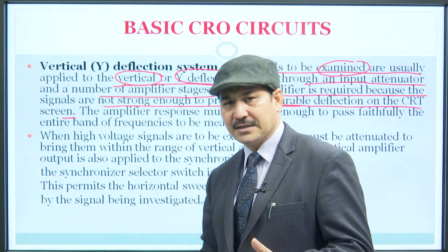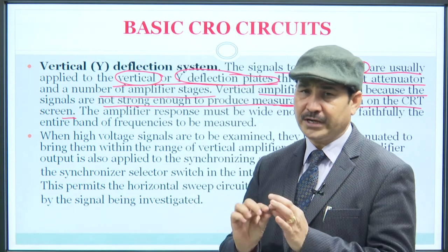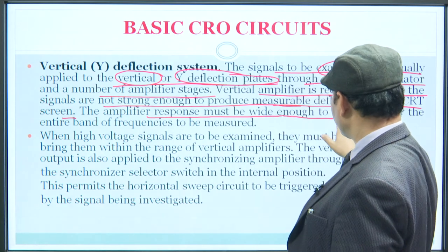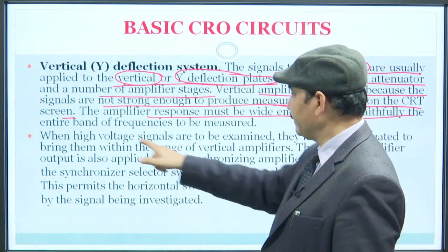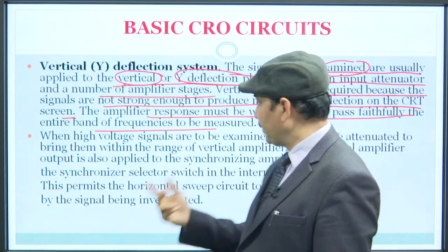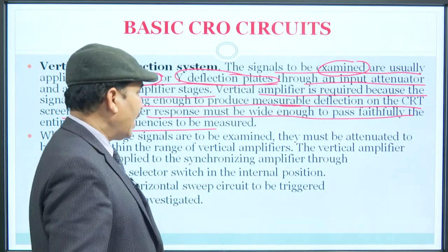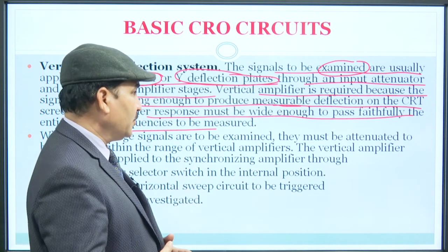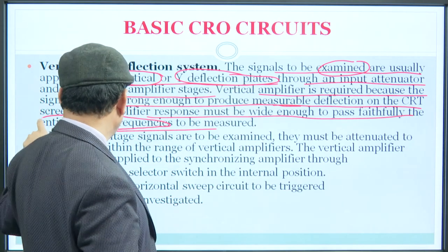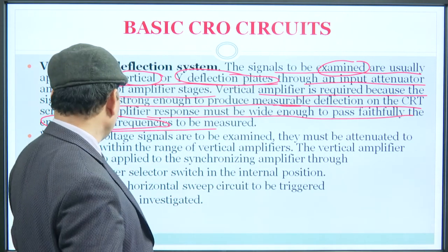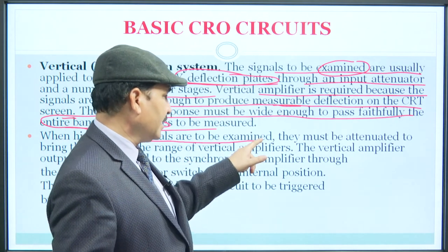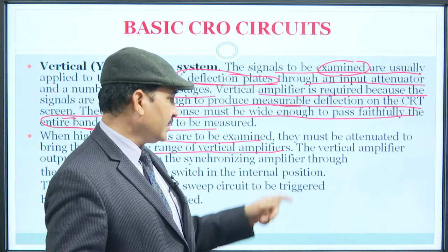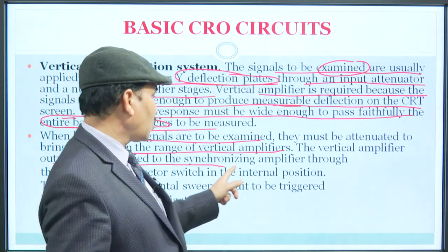If the signal is very large, it will primarily be attenuated; if required, amplification can also follow. The amplifier's response should be wide enough to faithfully pass the entire band of frequency to be measured. When high voltage signals are to be examined, they must first be attenuated to bring them within the range of the vertical amplifier. The vertical amplifier output is also applied to the synchronizing amplifier.